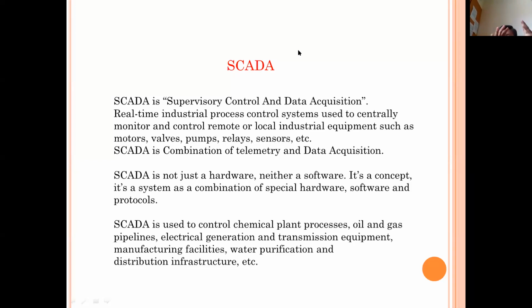So these 5 languages can be used for programming the PLC, but the more preferred language for programming the PLC is ladder logic. But when you come to the DCS, the most preferred programming is FBD, functional block diagram. So SCADA: we have the main PC loaded with software. Below that you have the RTU or the PLC. Either it can be an RTU or it can be a PLC. The PLC will collect the data from the field instruments. Okay.